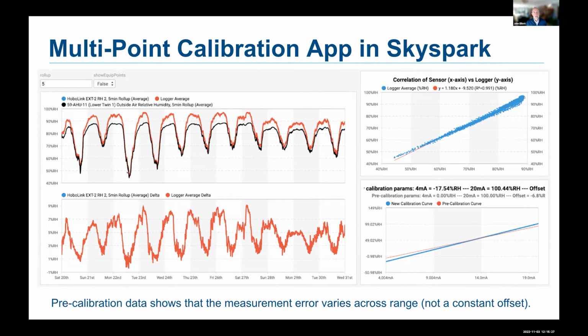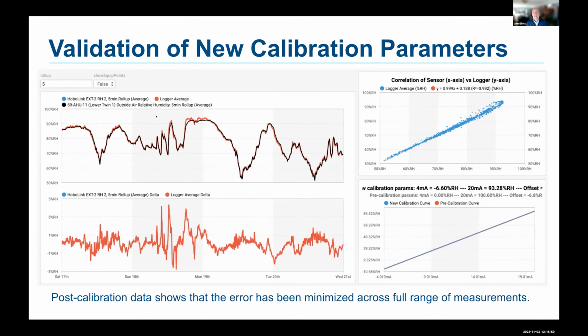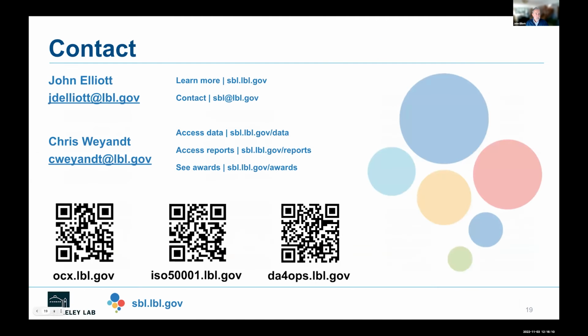So you can see this is a case where at some measurements, you have very good agreement between the logger and the sensor. And in this case, at higher relative humidity, you have significant disagreement by like 10%. So this is a case where you can't correct this with a constant offset. Through SkySpark, it's suggesting a new calibration curve in this case, or a slope of the calibration curve. And then we can apply that. And of course, you can use this same environment in SkySpark to check to see if your calibration is good. So this is post-calibration data in which we're getting good correlation across all measurement there. So those are a few little detailed areas that we're exploring related to our overall ongoing commissioning effort.